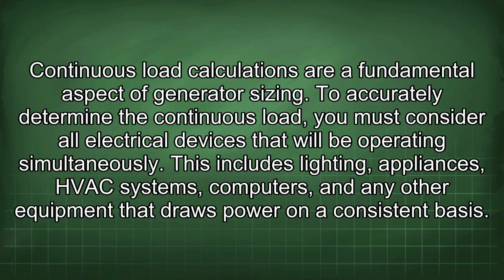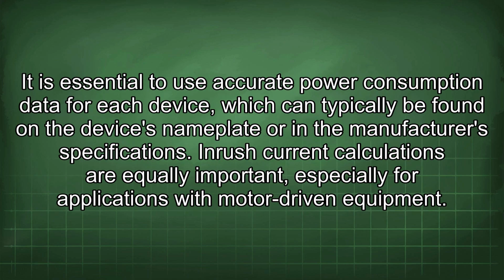Continuous load calculations are a fundamental aspect of generator sizing. To accurately determine the continuous load, you must consider all electrical devices that will be operating simultaneously. This includes lighting, appliances, HVAC systems, computers, and any other equipment that draws power on a consistent basis. It is essential to use accurate power consumption data for each device, which can typically be found in the device's nameplate or in the manufacturer's specifications.